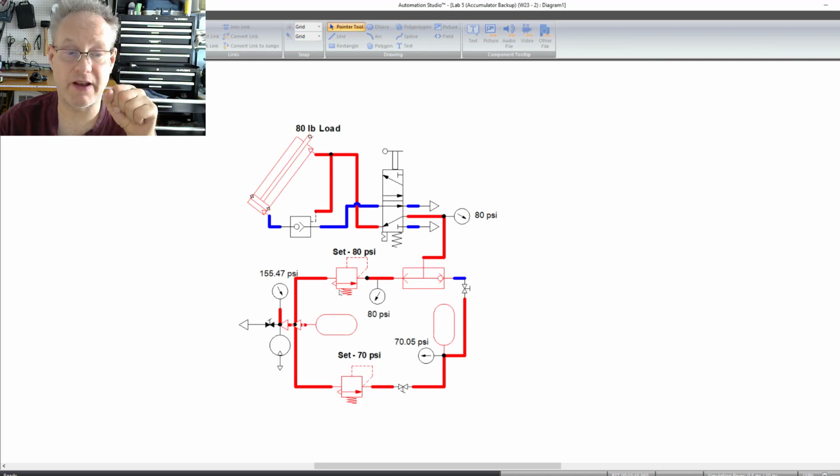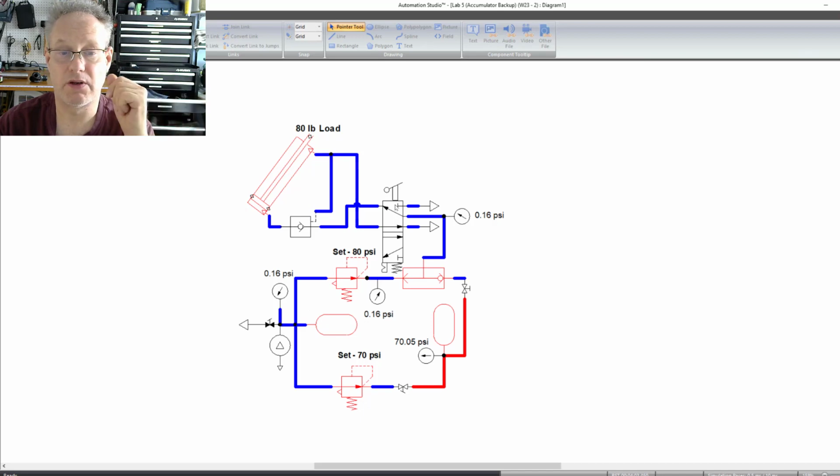So I'm simulating a failure here, and this failure is the system is open somehow, or it turns off, or whatever. The regulator dies, like I said before. So the pressure goes really low. Now the pressure here is low, and what I'm going to do is run this once, and you'll see it doesn't even move. And the pressure's gone down to 0 because I tried to use it, right? So it's not working. I'm going to turn my backup on.